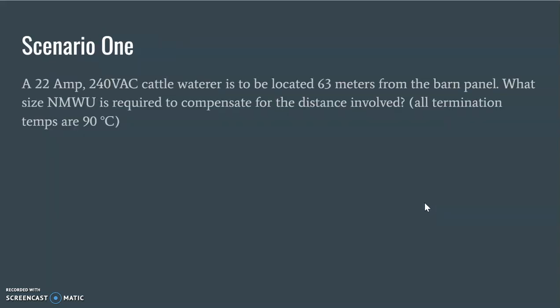Okay, so first we'll go through this scenario. We have a 22 amp load, it's a 240 volt cattle waterer, and its wire distance from the barn panel is 63 meters. We're going to feed this with some NMWU and we want to know what AWG size we're going to need for that because of the distance that's involved.